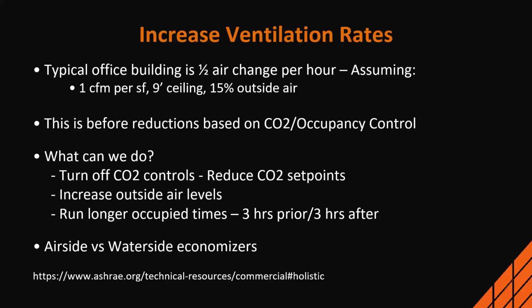The other thing is if I have an outbreak and I want to flush my building, but it's not the appropriate temperature, I can still ignore the temperature and flush the building because I have control to go at 100%. A lot of our higher office buildings, say a 20-story office building, normally that's going to be a water side system, and I'm going to have a water side economizer, so I'm going to get my free cooling through the water.